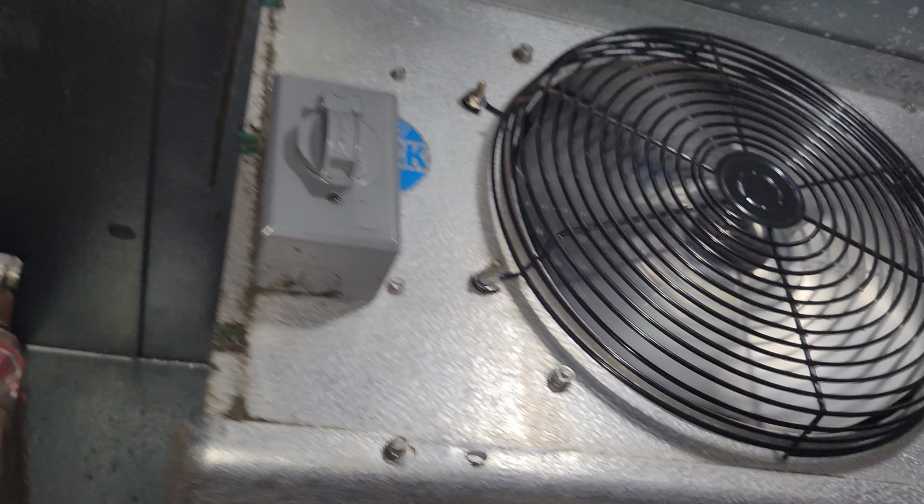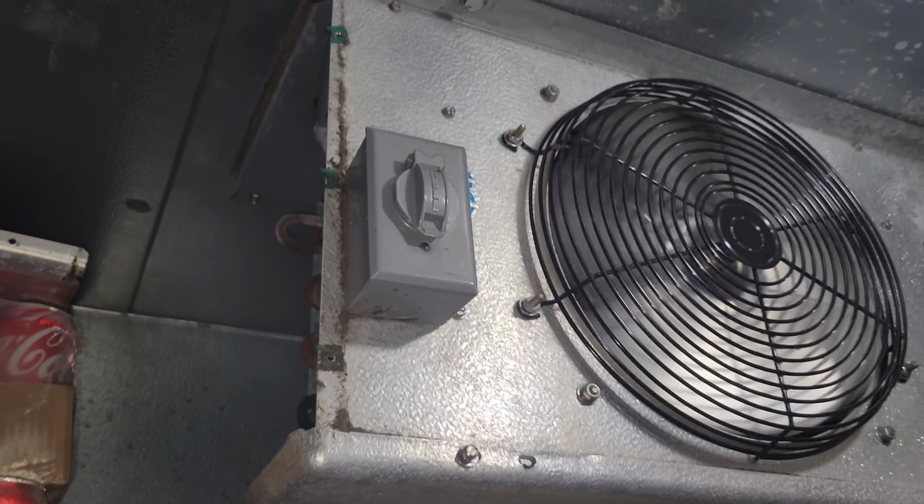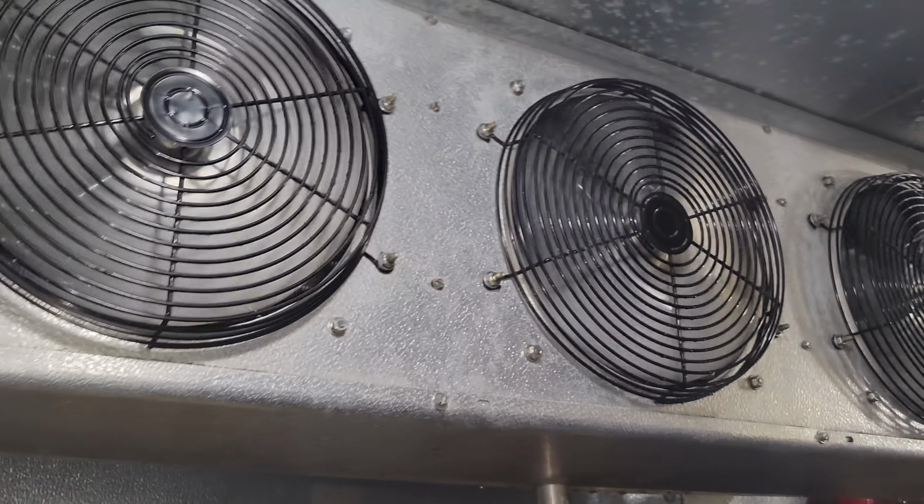So understanding the negative effect of having a fan switch that does not turn off the refrigeration circuit is very important. It can lead you to where the root cause could have been, or how it could have happened. Because, why was only one coil iced up here?